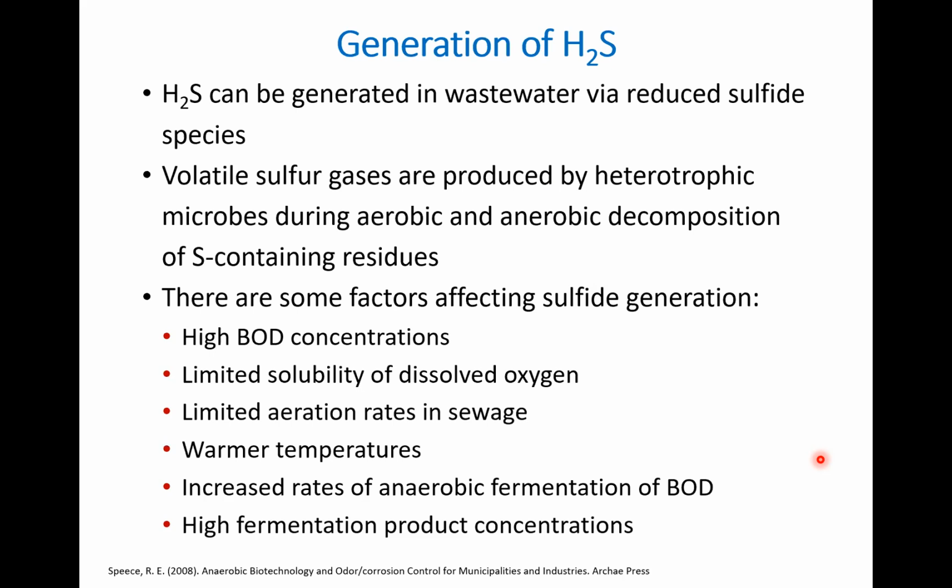There are many factors that affect the sulfide generation, for example, if you have high BOD, or biological oxygen demand, or you have limited solubility of dissolved oxygen. If you have limited aeration, this is related to the previous one, the solubility of dissolved oxygen.